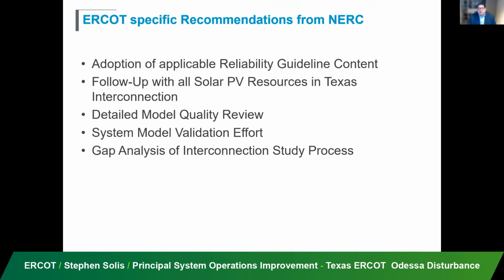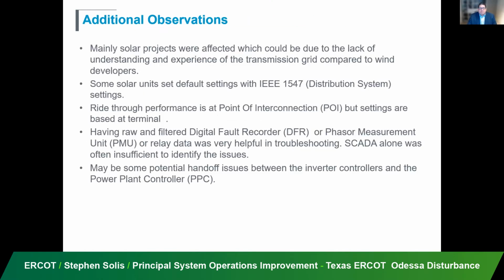So, we are working with specific issues that we saw due to this event, as well as looking at the modeling. For these types of issues, positive sequence models do not seem to be effective. We're hoping that better models and the requirements around that for the EMT models may allow us to have a better screening process through the new interconnections that are coming on. And so we're trying to get that in line so that we can screen and catch these issues before the solar resources come and interconnect.